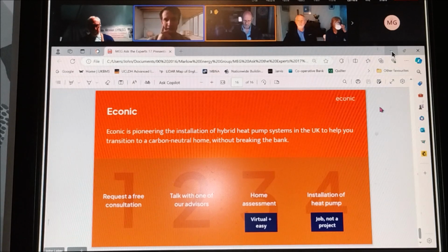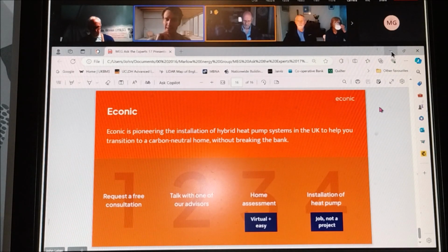That's number 1, right? And number 2 is what kind of flow temperature, so how efficiently you want to run your system inside your house. That also determines a little bit how many radiators you need to upgrade. The key thing for us is we're doing a heat loss calculation, and we monitor all of our heat pumps and have a feedback loop with the customer to understand real, empirically driven data in terms of what actually happens versus just us modeling.